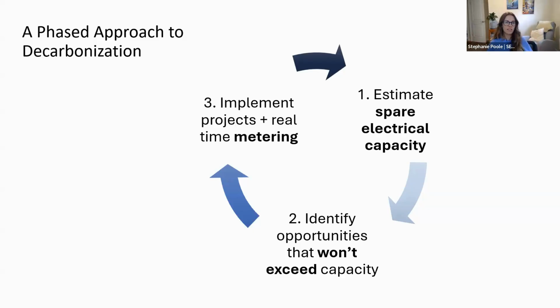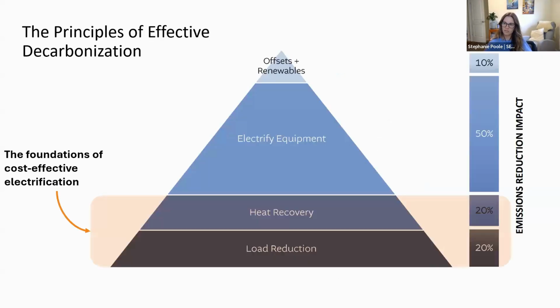But one thing you do want to consider is using real-time metering. I feel like every time I do a presentation, I say that, metering our actual load, but it is consistent within the industry, regardless of the RTUs versus domestic hot water versus boiler, any system is going to be oversized if you're using standard rules of thumb. So using real-time metering, maybe we'll just skip to the next slide and then I'll just mention that there's more information available, but some of the principles to effective decarbonization, this is just a really quick snapshot.